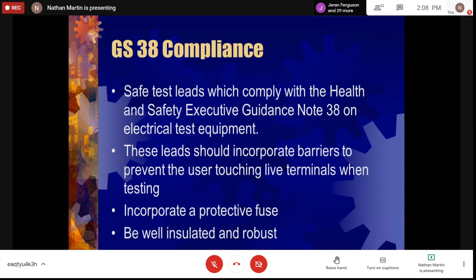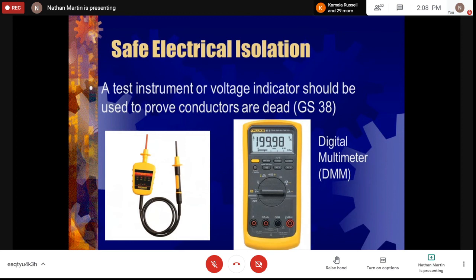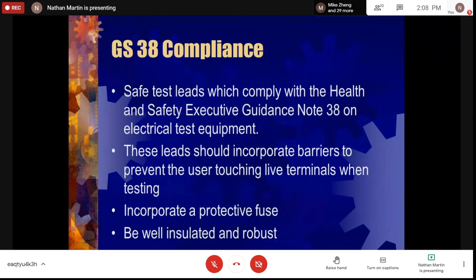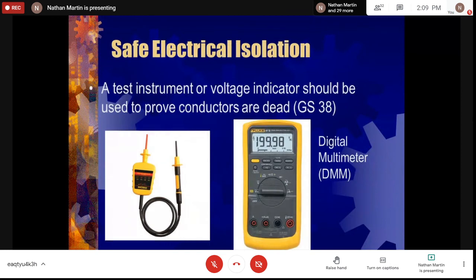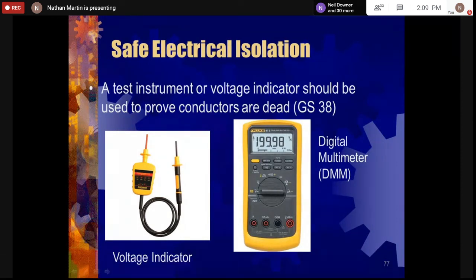The safe test lead must have a barrier - that little thing you see on the end of the test lead so your hand doesn't slip onto the circuit you are testing, even if you have moisture on your hands. It must also incorporate a fuse, so if you look at your meter test lead, on the part you hold, you will see it's rated 10 amp.